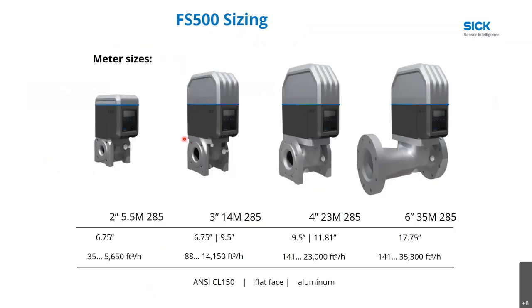Again, some more of the sizing, some more information here as we saw previously. One of the things about the 500 meter is that it's ANSI 150. Currently, that's the only rating that we have, so it's only good to approximately 285 PSI. It is aluminum body and has a flat face on it.